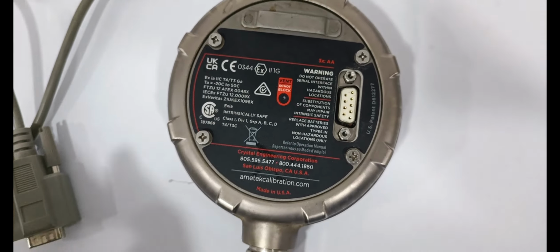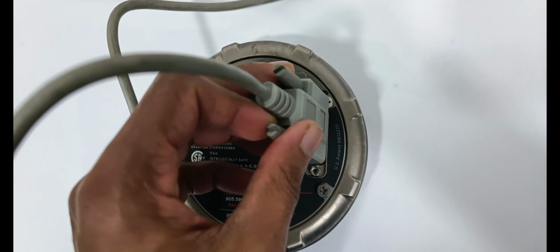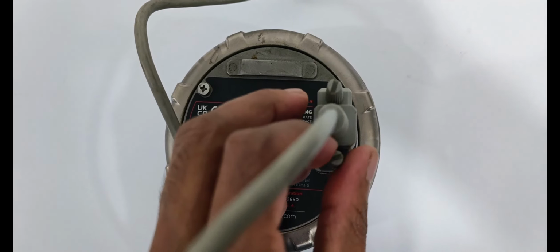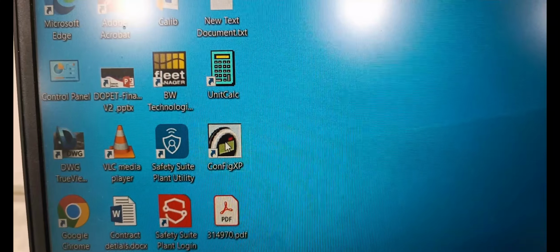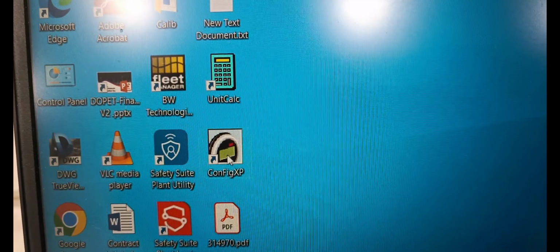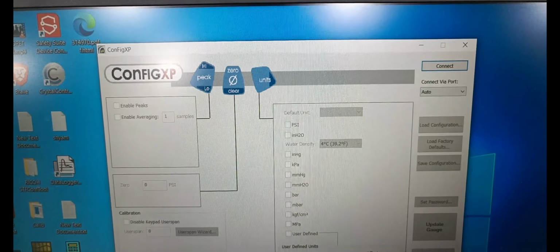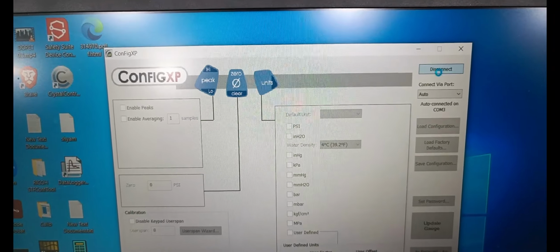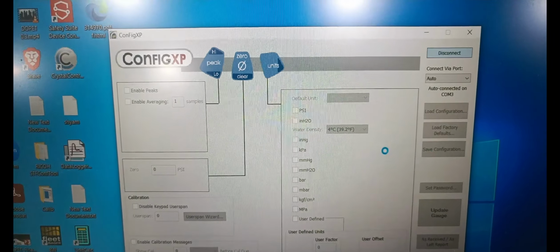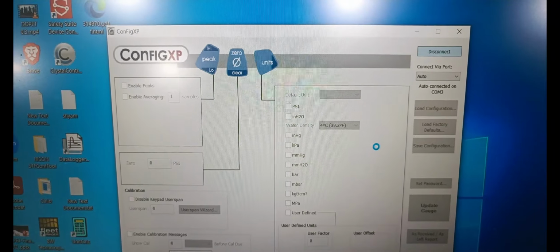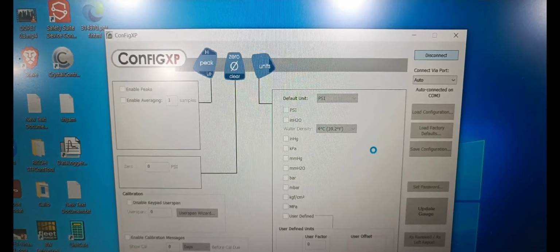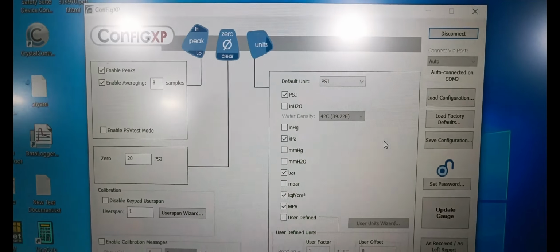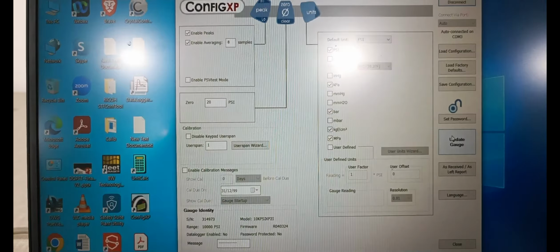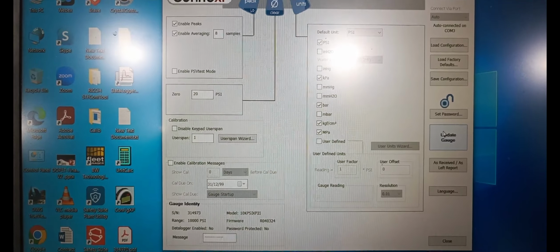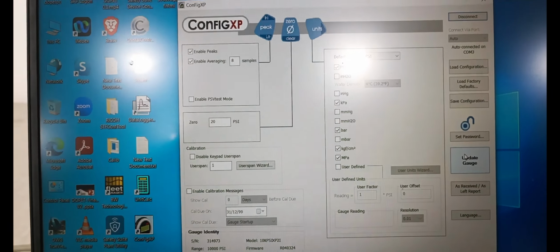Next, we connect the serial RS232 cable to the unit. The software is already installed on the PC. Open the software. Connect. Okay, now the digital reference gauge data is showing in the software.